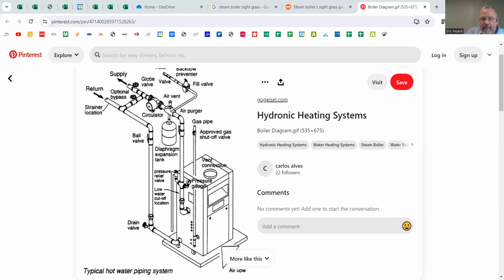Okay. So there's a couple other things that we see here. It does show a pressure gauge on the boiler. Sometimes there are pressure gauges, sometimes there are not. My experience is most of the time they don't work after a fairly short time. The exception is those ancient ones. You'll see 70-year-old ones, 60-year-old ones, 50-year-old ones that still work just perfectly fine. So I'm making a case for the elderly here, guys. That's all of us. Yeah, they don't make anything like they used to. That's right. Not as good as it used to be, right?